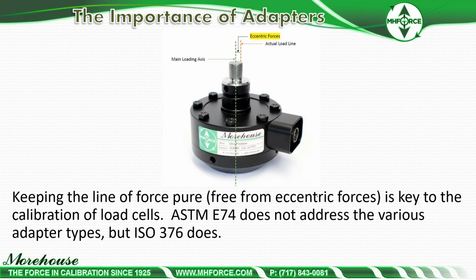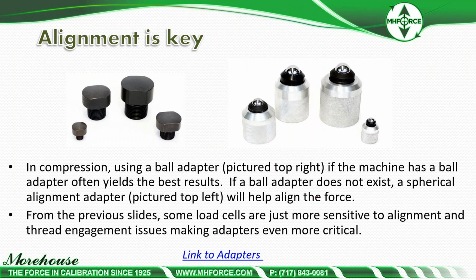They say in section A.8.4 about having two ball cups, two ball nuts. They give you real good guidance. In compression, alignment is the key. So using a ball adapter, picture top right, if the machine has a ball adapter, it often yields the best results. This is primarily because of centering. Other things could be friction, and some other things, less surface area, less friction in the frame. If a ball adapter does not exist, a spherical alignment adapter, picture top left, will help align the force.